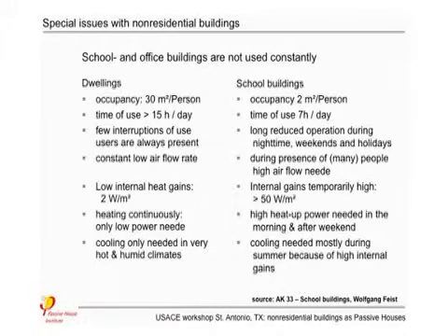But first of all, some special things with school buildings, which I already mentioned. In dwellings, you have about 30 square meters per person available. In school buildings and meeting rooms like this, when all people are there, you have about 2 square meters per person. In dwellings, you use it all day long. In school buildings, only before noon or maybe until 18 o'clock in the evening. In dwellings, continuous operation; in school buildings, reduced operation during nighttime. You can save some electricity for the ventilation system.